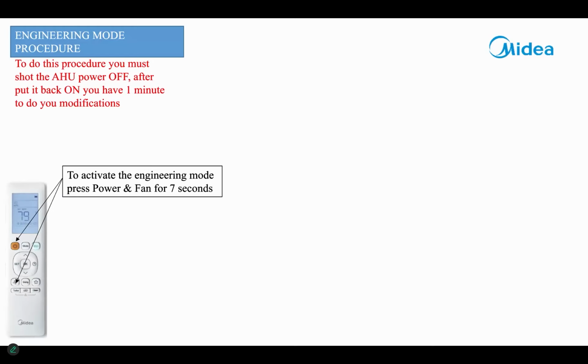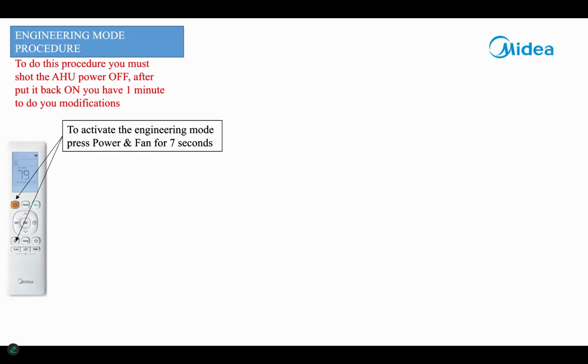So, engineering mode. I'm going to start by saying, to get into engineering mode, you have to turn the system off by the breaker on the AHU, and then turn it back on. The system has to be in standby mode, or turned off at the remote or the thermostat or the wired wall control. Once you turn the power back on, you have 60 seconds to get into engineering mode.